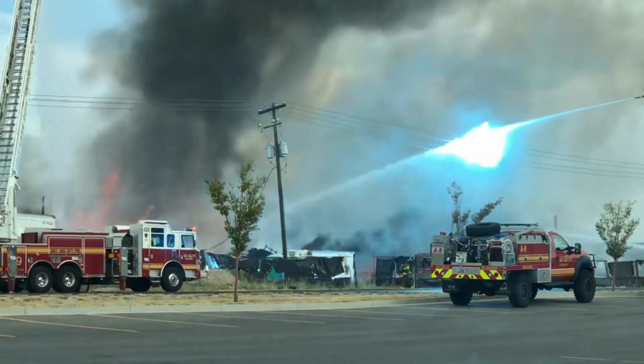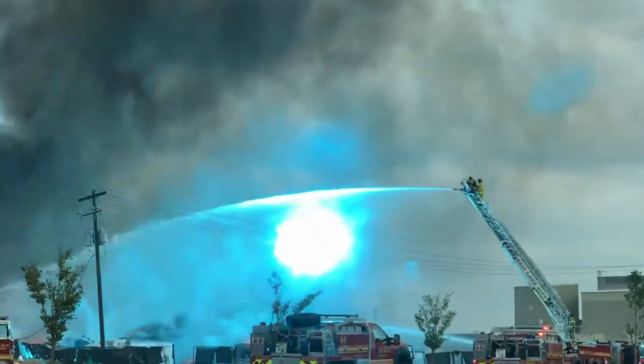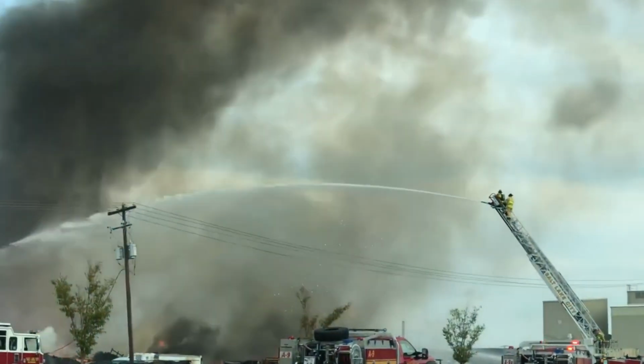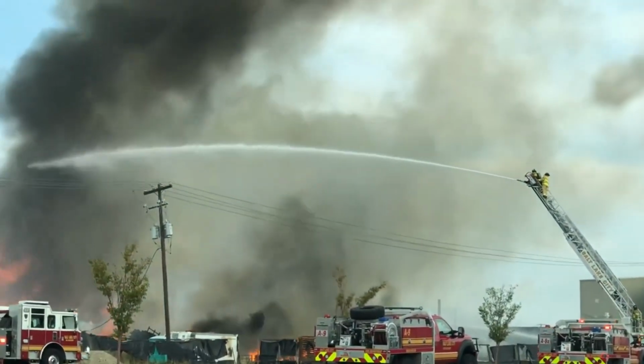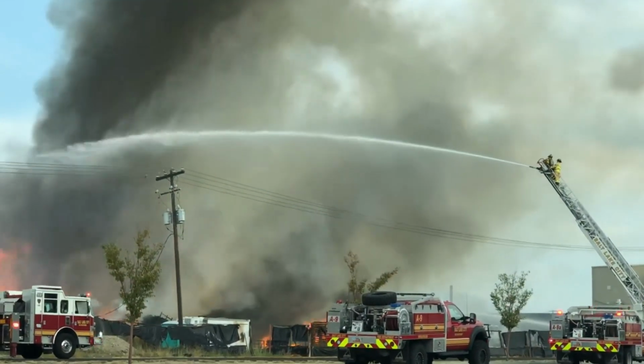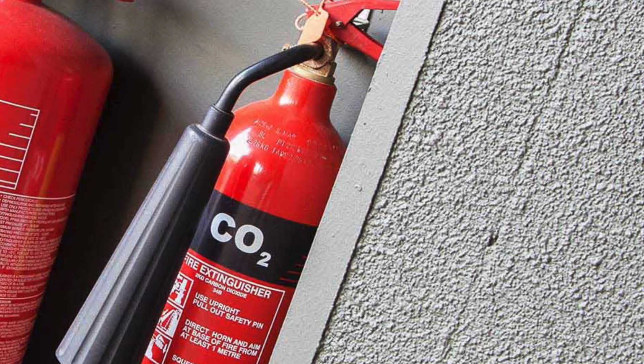So what classes of fires are some extinguishing agents not suitable for? Let's look at electrical fires. Do you know that it is unsafe to use water or foam for electrical fires? Water and foam are good conductors of electricity, hence can lead to electrocution or death if not careful. Also, even though dry chemical powder can extinguish electrical fires, the powder component can damage electrical appliances, hence only used as last resort when there is no other extinguisher. The best fire extinguisher for electrical fires is CO2 extinguishers.